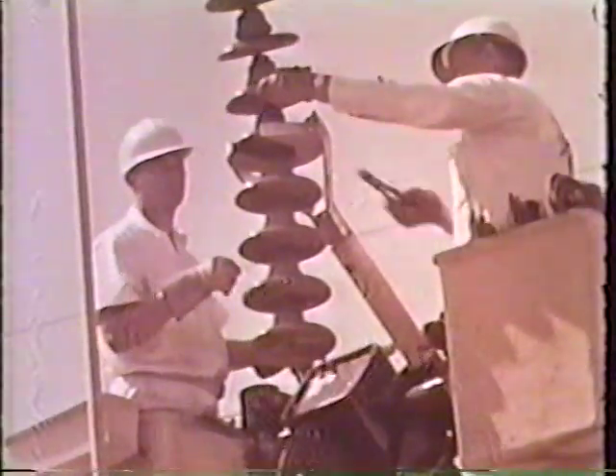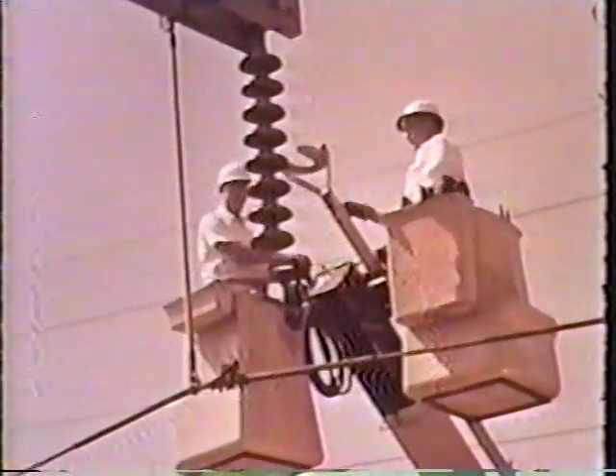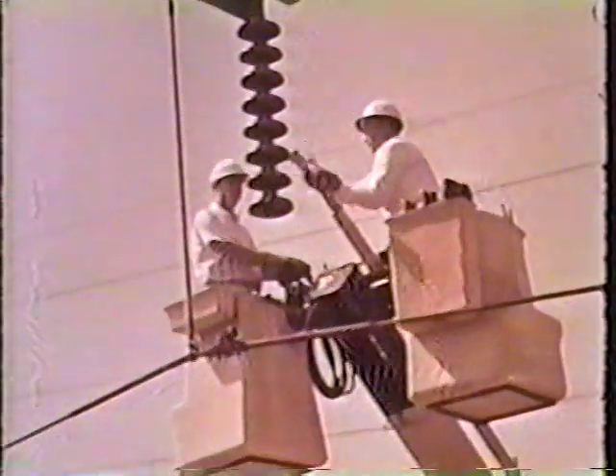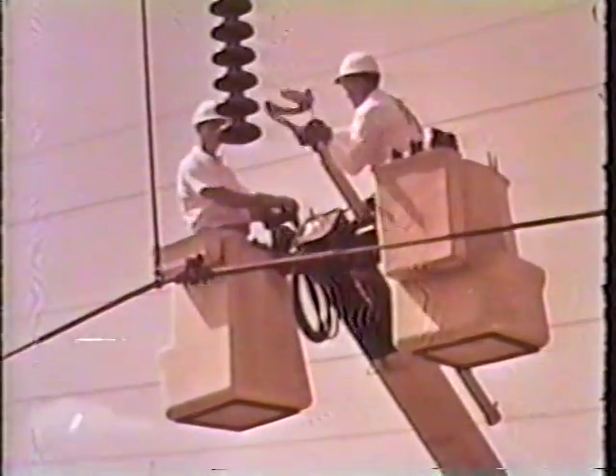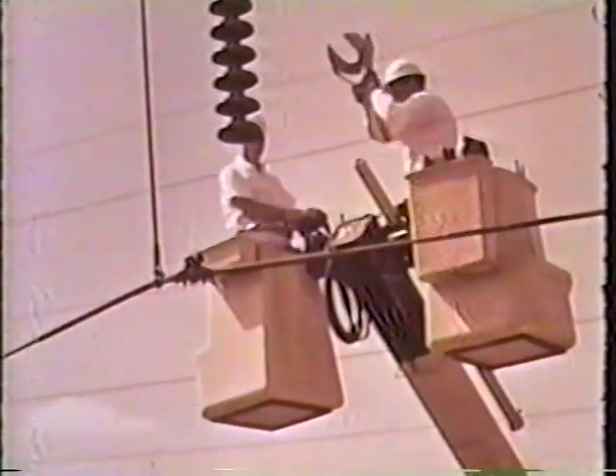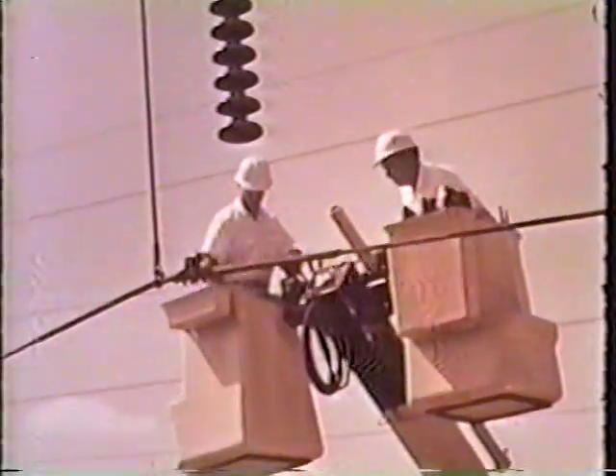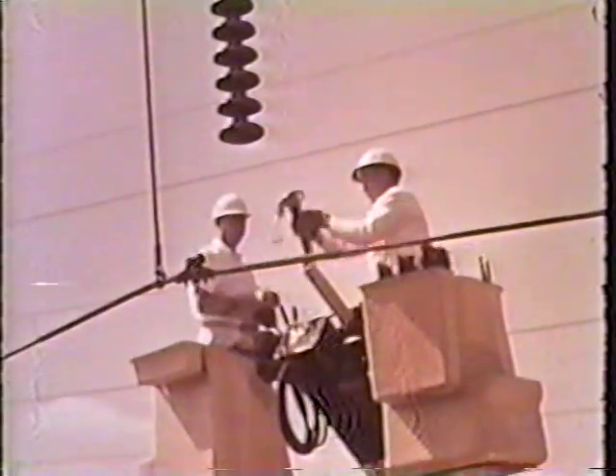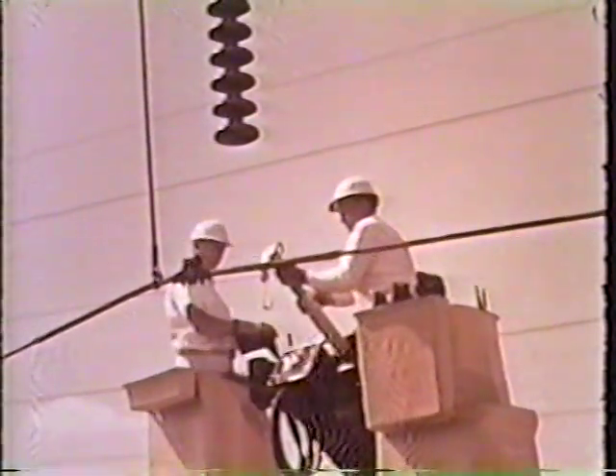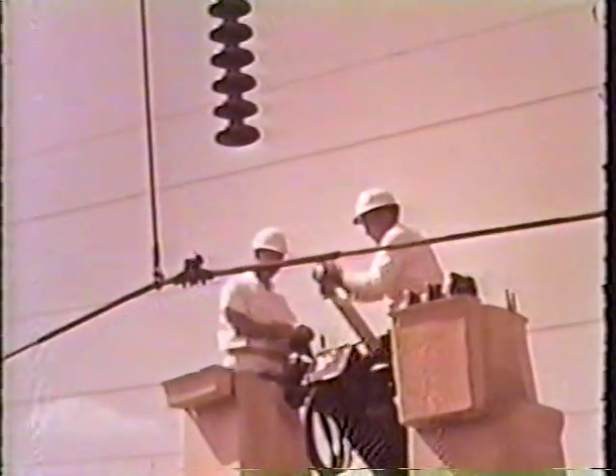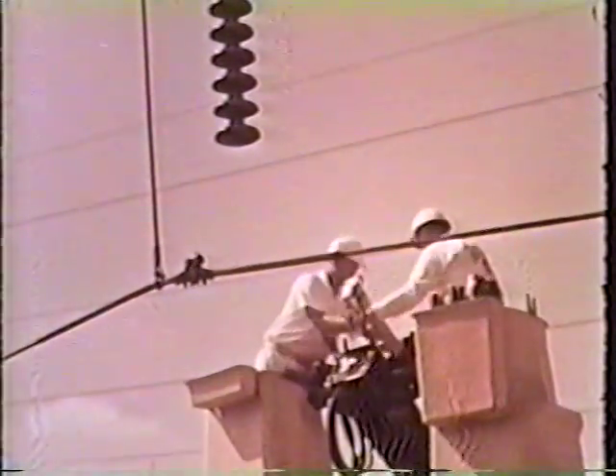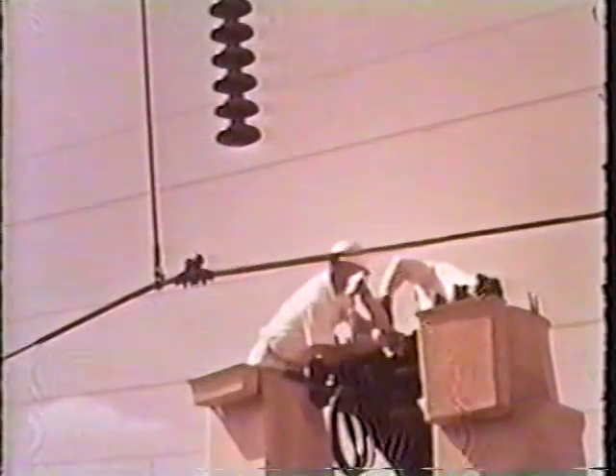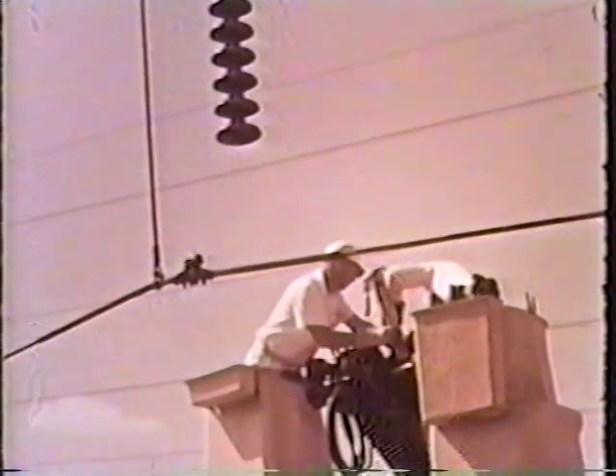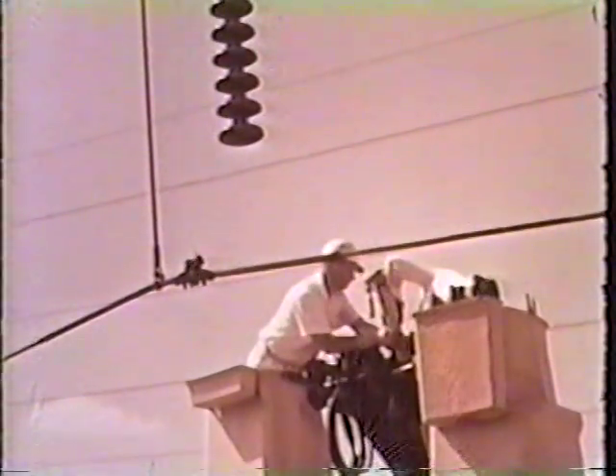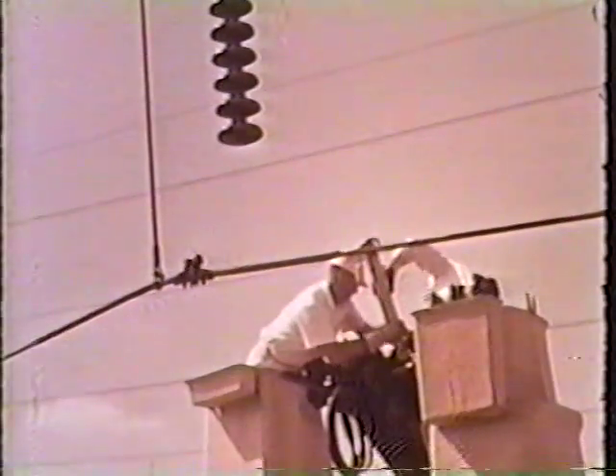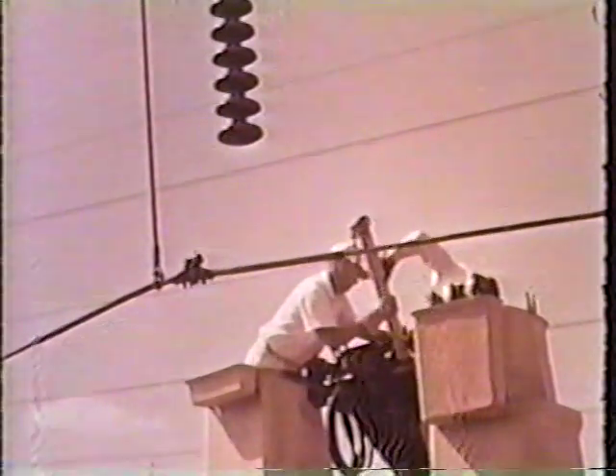Demonstrating again the operator's precise control over the movements of the elbow. The hydraulic cylinders that actuate the boom and elbow are double acting, so the arm is raised and lowered under power with positive control all the way. If the hydraulic system, which has a 5-to-1 safety factor, should fail, check valves prevent any movement of the arms. In such a case, oil pressure can be released manually to lower the bucket safely to the ground. The hook is replaced in the pivot boom, and the boom is rotated and extended.